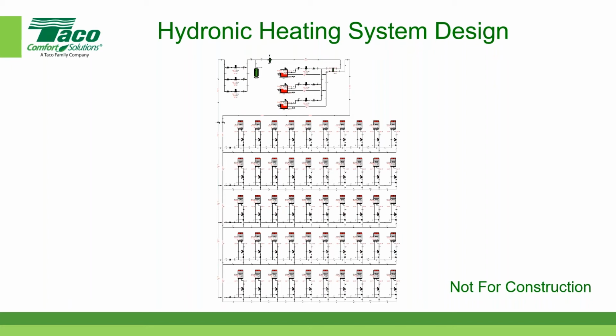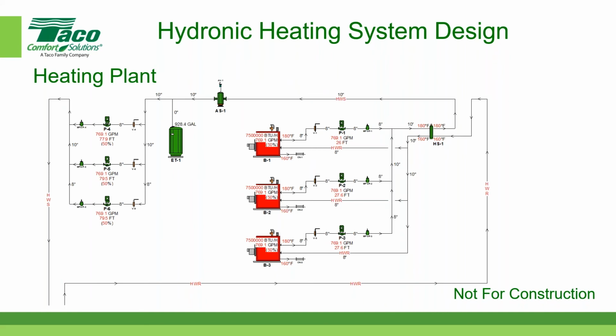So let's zoom in now and look at just the boiler plant. So here we have 3 boilers, and I have made somewhat of an arbitrary decision. I can tell you my logic in a minute. Each boiler is sized at 50% capacity, which means I have redundancy. That means that if at any moment in terms of its operating, I could lose a boiler, and if I had my peak heating load, I would still have 100% capacity.